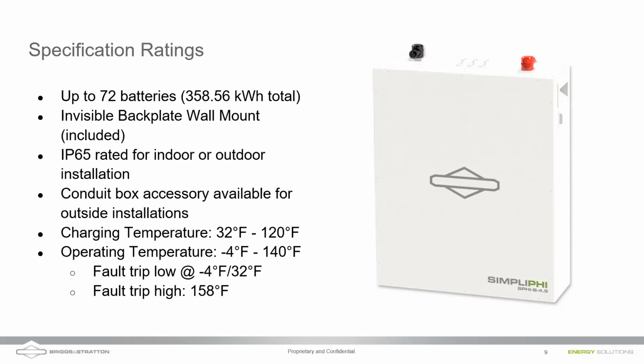And what I would recommend here is either you install the unit indoors or you simply convey to the customer that they should understand that in cold temperatures, their system is not going to allow charging, or it's going to allow charging very slowly. So as this unit gets closer and closer to 32 degrees Fahrenheit, it will tell the inverter to ramp down charge current more and more severely as it gets colder and colder. And then when it reaches 32 or below, it's just going to disable charging completely. It's still going to operate. It's still going to provide power to the customer's loads. But again, there's no charging, so they may run out of electricity at some point. So that's something to keep in mind for outdoor installations that are in cold environments.